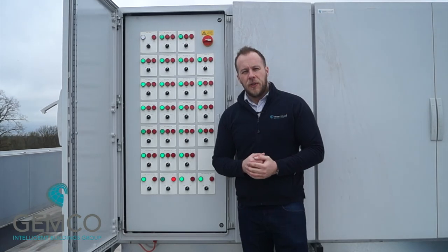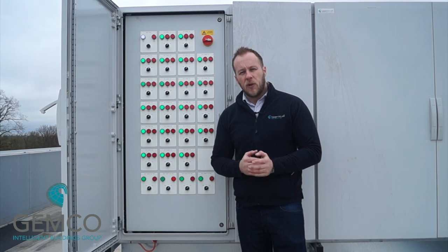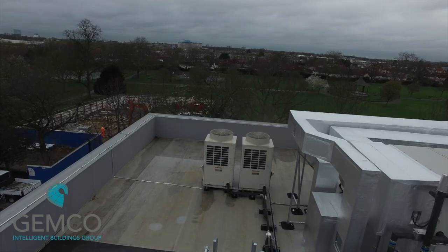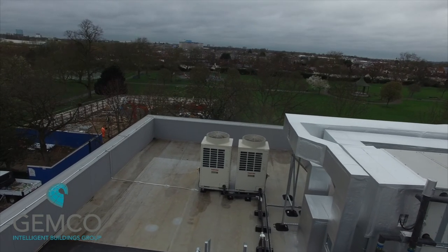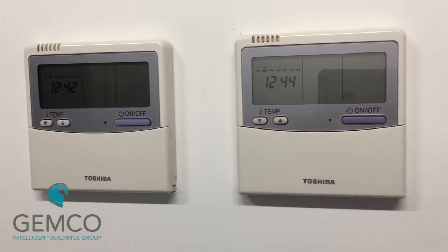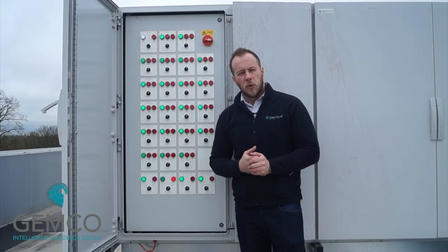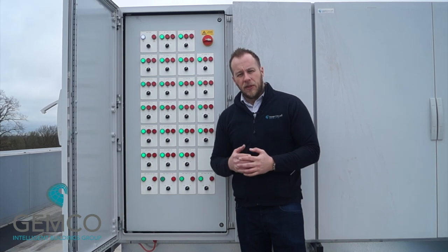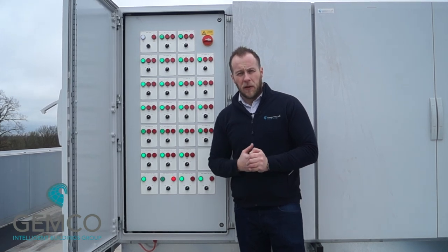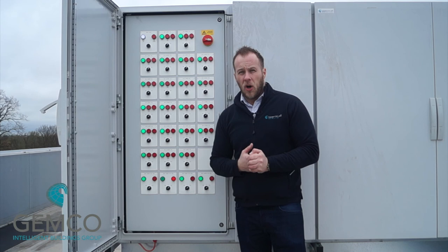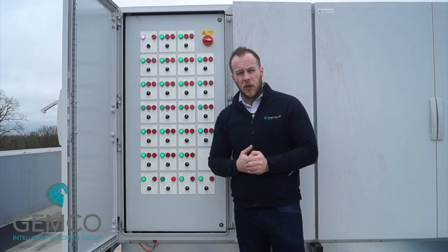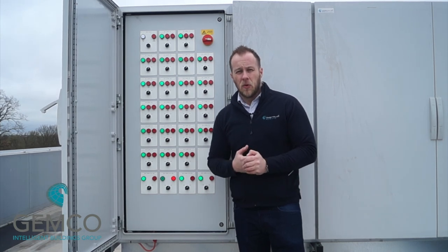The reason I said that units 8, 9 and 10 were slightly different is because they've got a DX coil built into them that's part of the AC system, and these units can be used for heating or cooling. So the set point of 21 degrees will be used to maintain the temperature of the supply, and if it's hot outside and you need some additional cooling, then these units are able to cool.